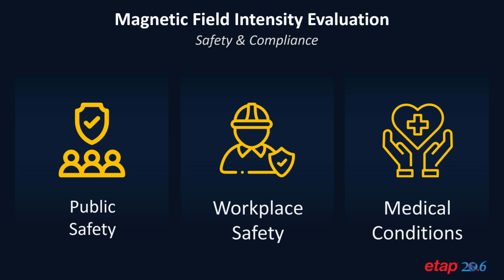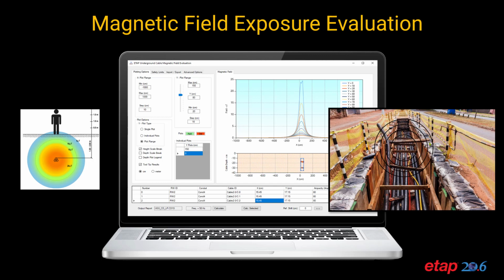The health and safety aspects of the analysis are a comparison of the calculated field intensity against the selected magnetic field exposure limits for a worker, the public, or any individual with a medical condition that is sensitive to electromagnetic field radiation. The magnetic field exposure module is integrated into the underground raceway system. By calculating the current flowing through every single conductor or entering that value, the program can determine what is the magnetic field strength around these cables.